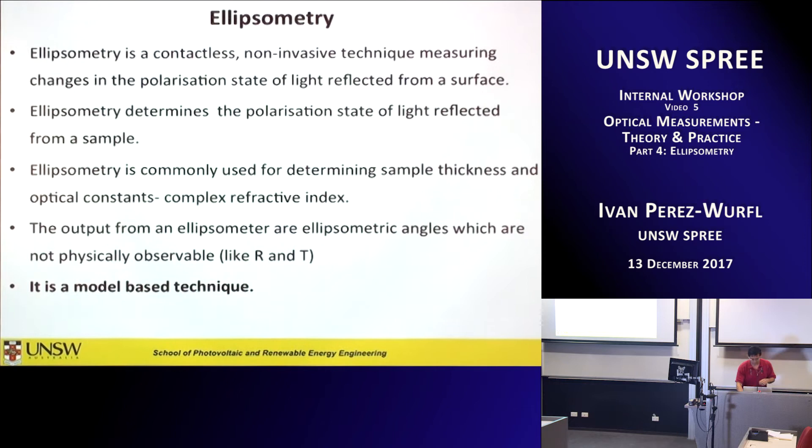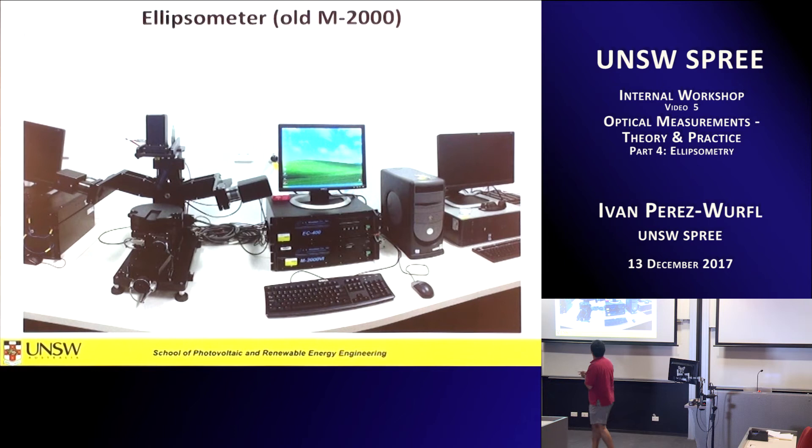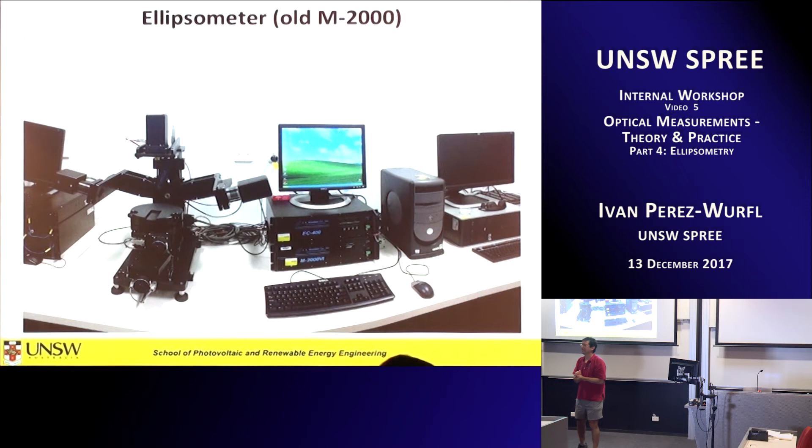Very specifically, the ellipsometer that we have is an M2000 — it's a very old version. The current model of the same instrument changes the angle automatically, which is the one thing we cannot do. But it's actually a really good instrument.